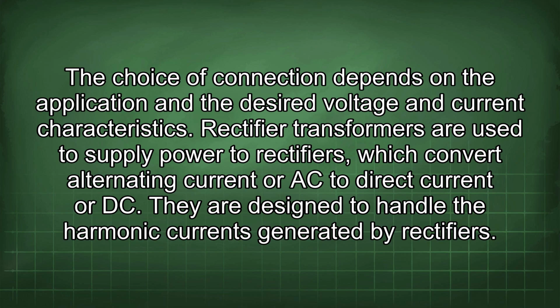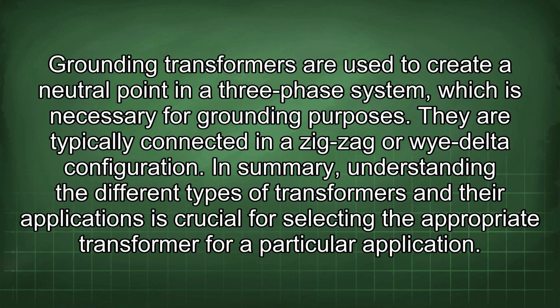Rectifier transformers are used to supply power to rectifiers, which convert alternating current or AC to direct current or DC. They are designed to handle the harmonic currents generated by rectifiers. Grounding transformers are used to create a neutral point in a three-phase system, which is necessary for grounding purposes. They are typically connected in a zigzag or Y-delta configuration.